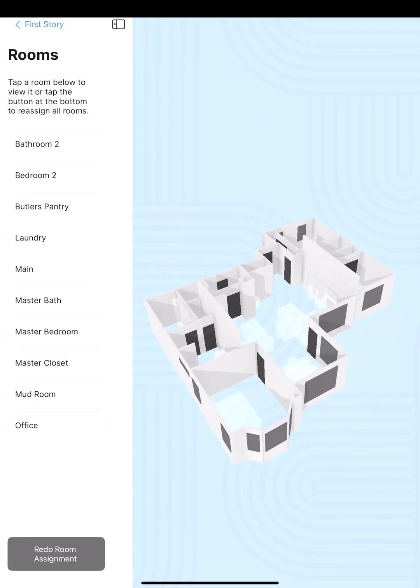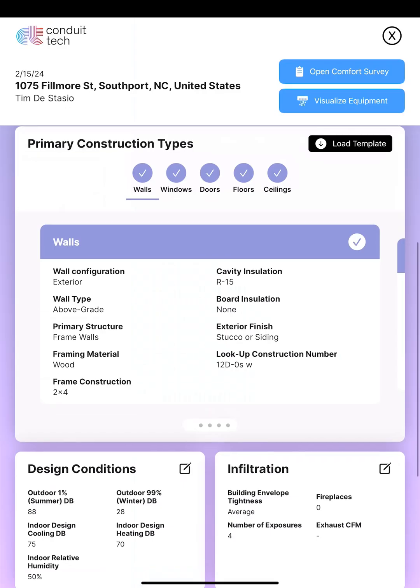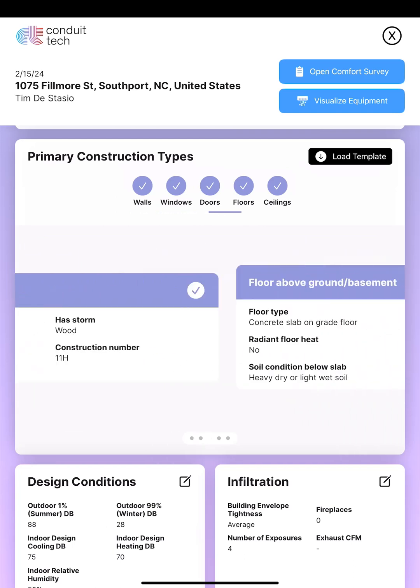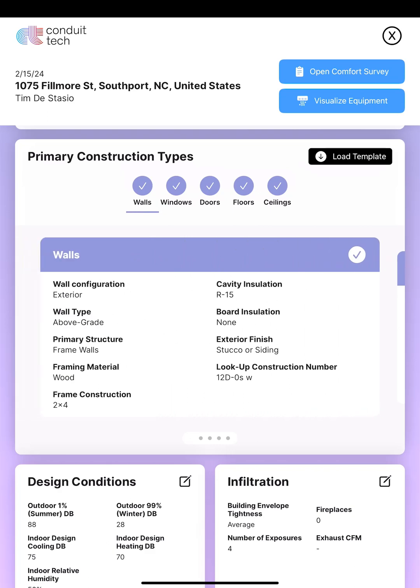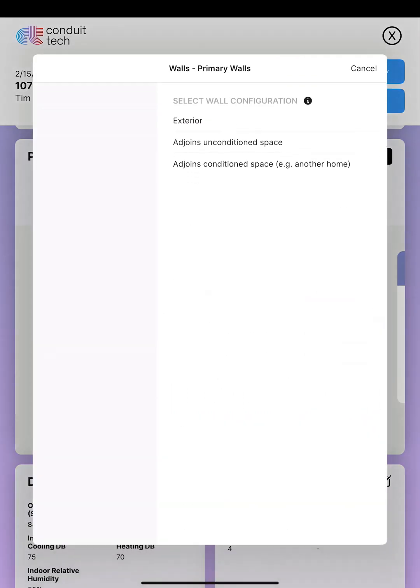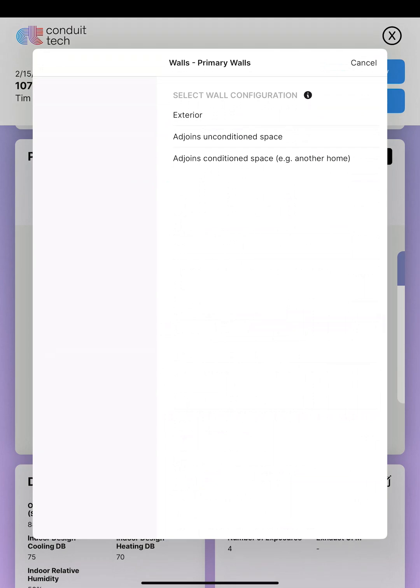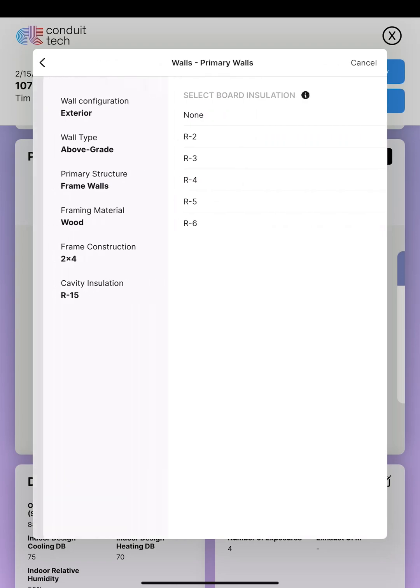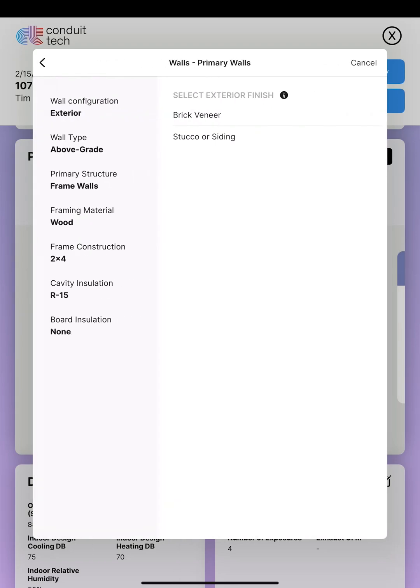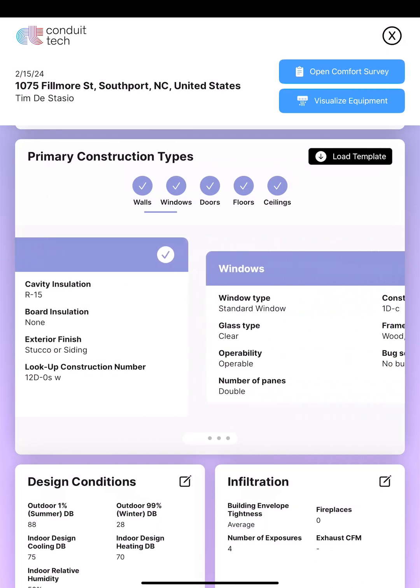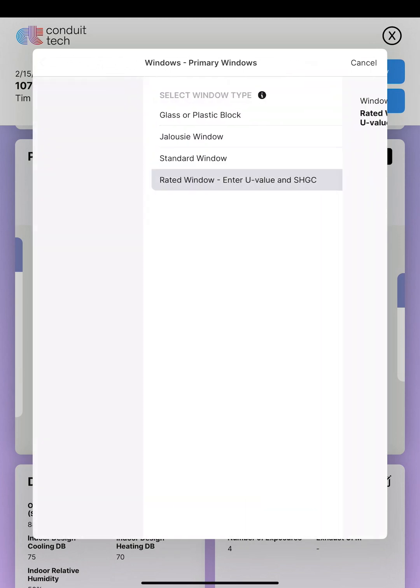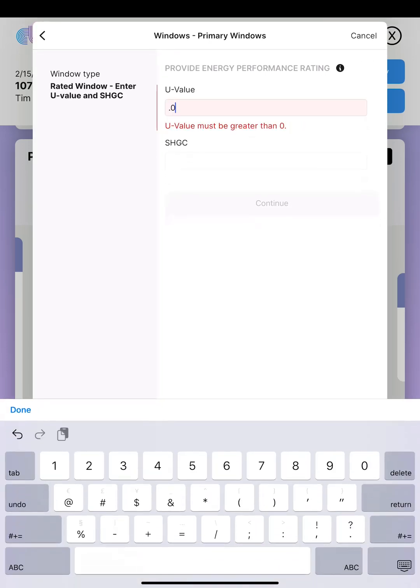Here's my finished scan. If I need to edit any of the rooms I've created, I can — and we can always go back to it. The next thing we need to do is configure room components: walls, windows, doors, and floors. For walls, you can set up templates so you don't have to build them from scratch every time. You've got different choices of exterior walls — above-grade basement, frame walls, wood. In this case I've got two-by-four, R15, no board insulation with siding. For windows, we could choose a standard window, but since I have the ratings for my newer house, I'll go ahead and put those ratings in.